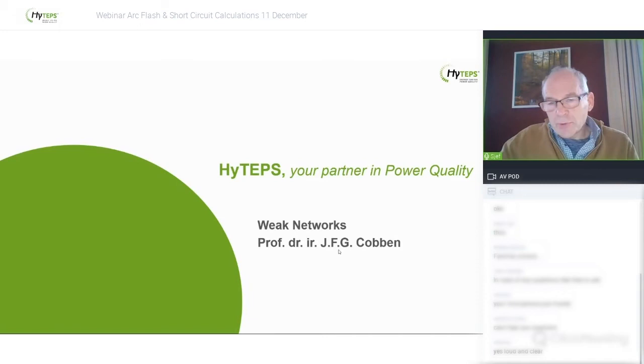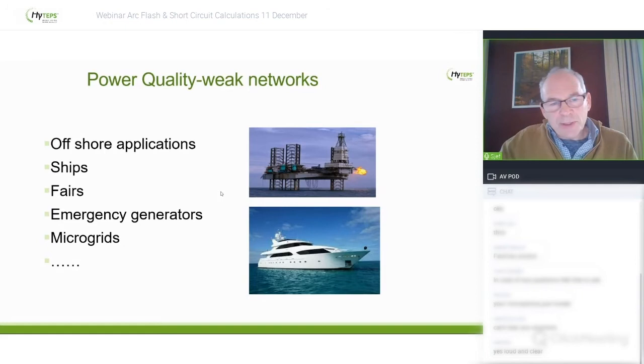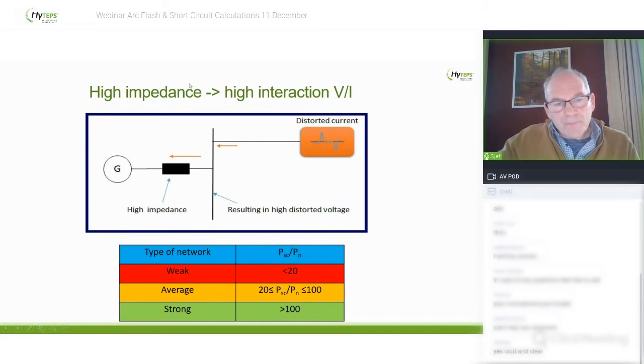My presentation is about weak networks, and I'm trying to explain why power quality at ships, or at weak networks in general, is a topic that should be studied and analyzed. Weak networks can be found in all installations not connected to the public network: offshore applications, ships, fairs, emergency generators, micro grids. Looking to the future, networks with storage solar systems and wind parks could also be disconnected from the public network and operate as a micro grid. All of these have the problem that the impedance of the network is quite high.